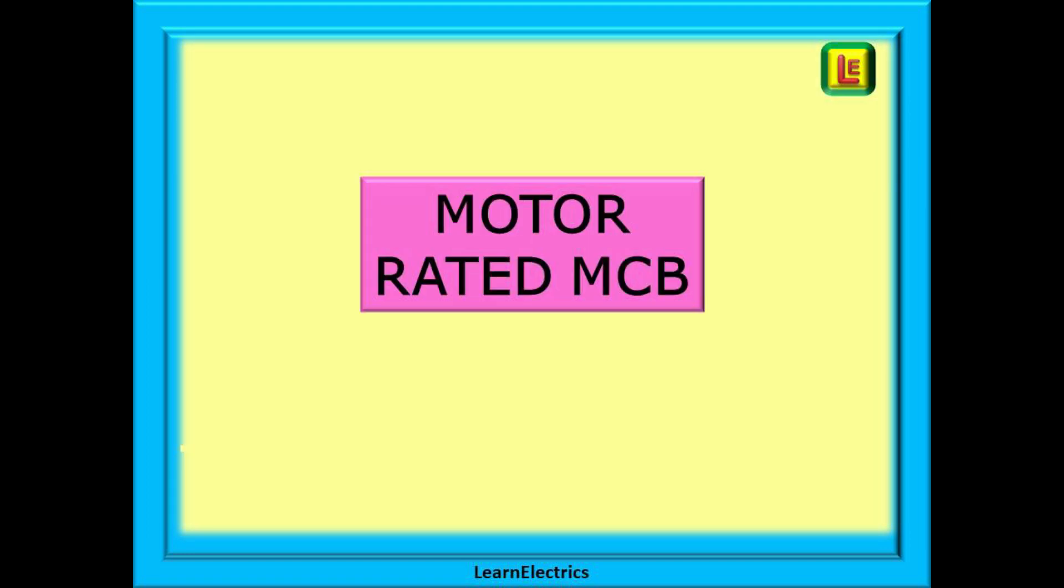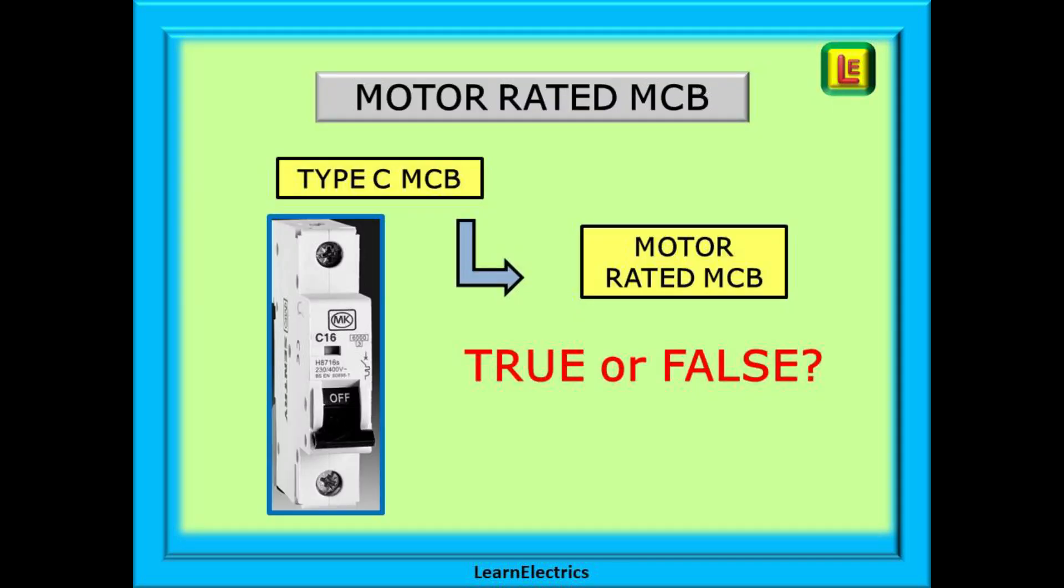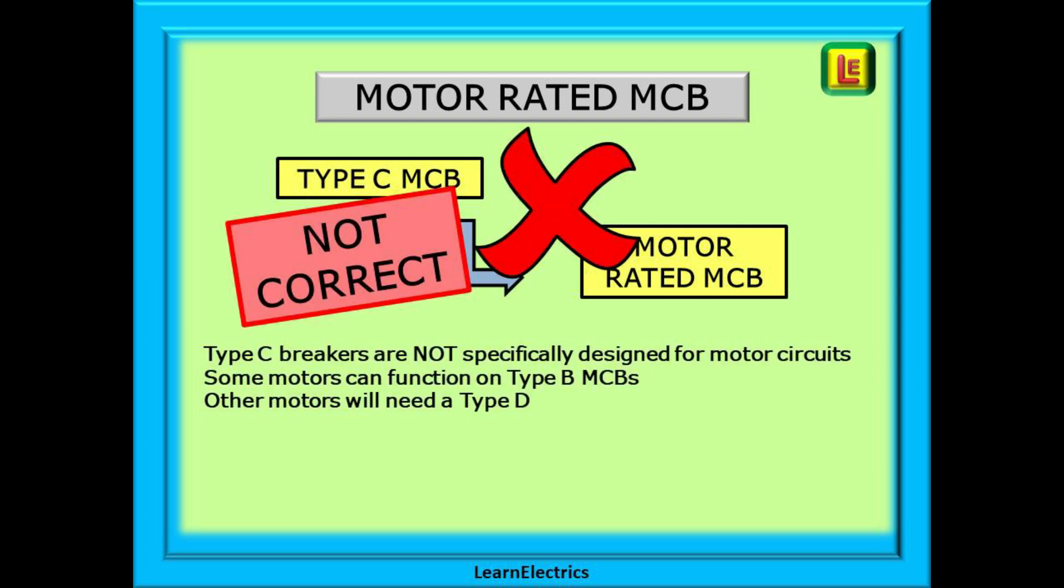Before we go let's consider a motor rated MCB. You will sometimes see type C breakers advertised as motor rated MCBs. This seems to indicate that every motor circuit should have a type C MCB. This is not correct. Type C breakers are not motor rated devices. Type C breakers are not specifically designed for motor circuits. Yes we can install a motor on a type C but some motors can function just as well on type B MCBs and at other times a motor will need a type D. We always install the MCB that is correct for the job.